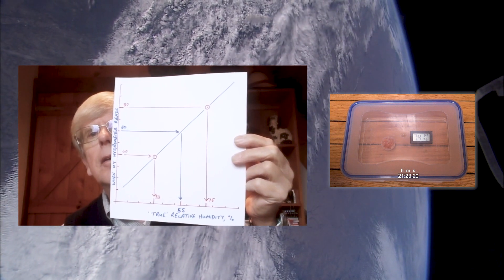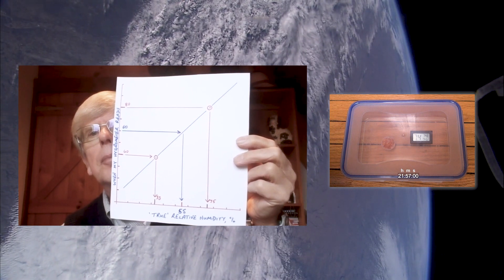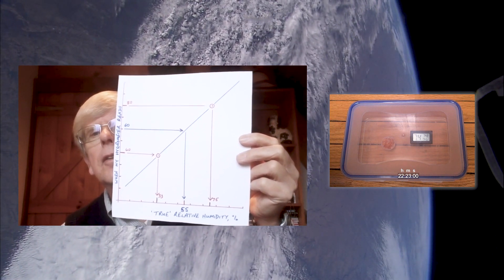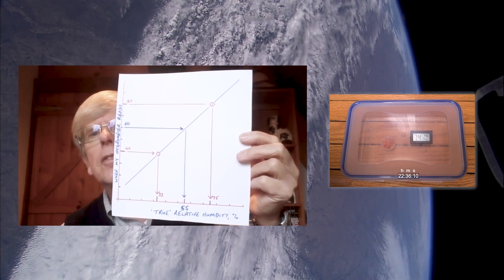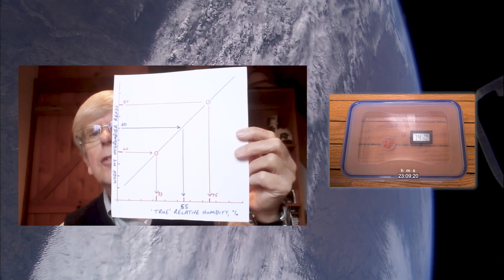Pack it up in some foil or whatever you do to keep it equilibrium at that humidity, and send it off and you can be assured then that your customer will find that it's arrived with a relative humidity around it of 55%. So that's why we do bracketed calibrations.